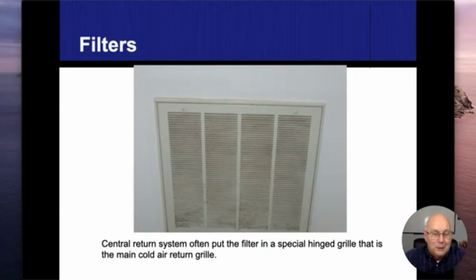So what that means is if I got a 70-degree temperature in the house and I got a 30 to 60 temperature rise, that means I should be between 100 and 130 degrees. So I'm going to take one of those dial thermometers or turkey thermometers or whatever other device I have. I'm going to measure either the air where the filter is, which is pretty much the room air, and you could see that on your thermostat. And then I'm going to go above the plenum and measure that temperature there as well. And if I'm too high, I like to remove the filter and see if that lowers that temperature back down to normal. Because if that filter is restricting the airflow and now my circulation air is slowed down coming across that, it's going to absorb a lot more heat.